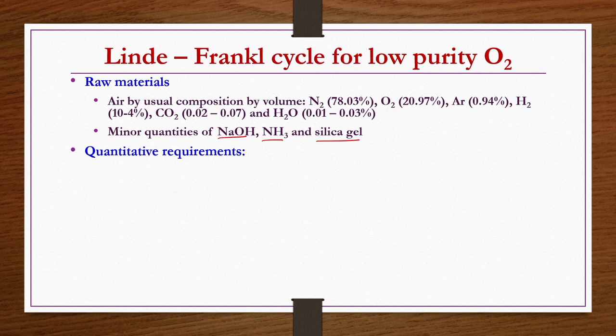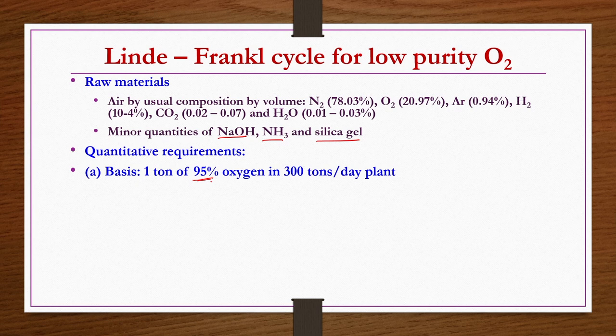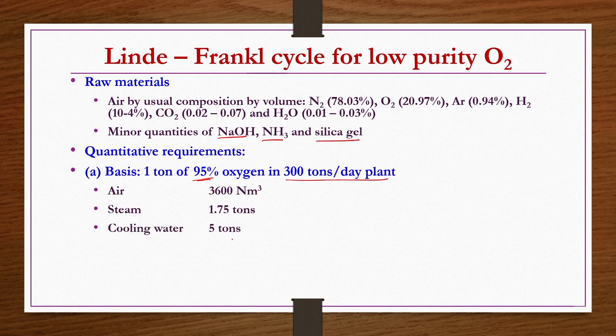From a quantitative requirements point of view, to produce 1 ton of 95 percent pure oxygen in a 300 tons per day plant, 3600 normal cubic meters of air is required, 1.75 tons of steam, 5 tons of cooling water, and 450 to 480 kilowatt hours of electricity. Plant capacity is usually between 50 to 500 tons per day.